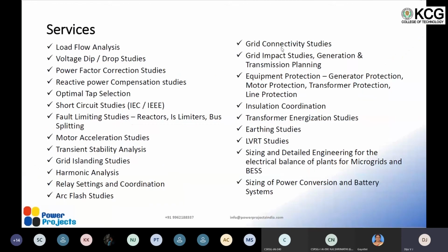And these are the main services we do. Generally, like most of the services are studies from our side. So you can see we deal with load flow analysis, then voltage dip drop studies, power factor correction studies for an industrial plant, reactive power compensation studies, again mostly for industries, and optimal tap selection for the distribution system.